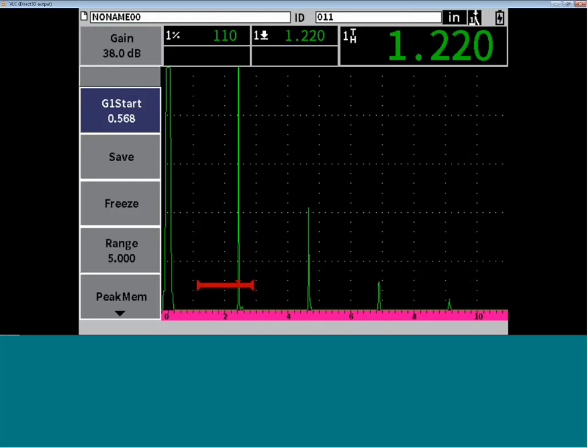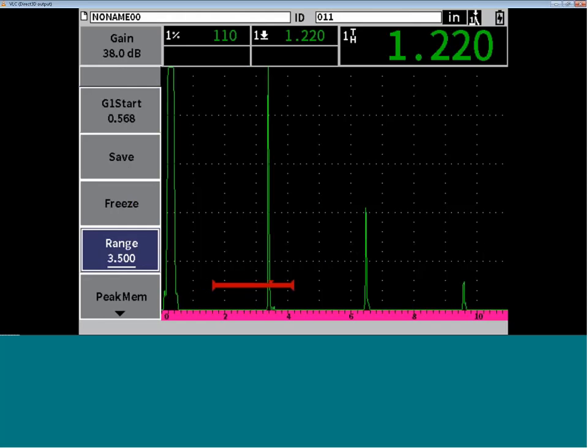Now, since the EPOCH 6LT is designed to have only 4 main navigation buttons, it does depart a little bit from the traditional EPOCH design focus on direct access keys to our main requirements. But this sidebar menu provides exactly that, that you may have been used to in your EPOCH 4, EPOCH XT, or EPOCH 650 flaw detector in terms of direct access to key inspection controls. So through this sidebar menu, we have access to your gate adjustment, to functions such as save and freeze, and also range adjustment. You can navigate through these adjustments using the knob, and through a simple press of the Enter key, you can invoke adjustment of that value and adjust things like range down to exactly the acoustic range that you're looking for.